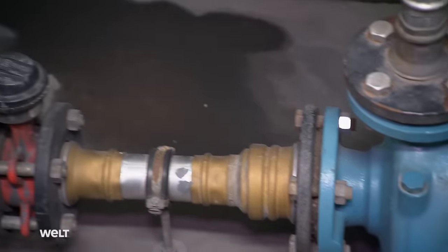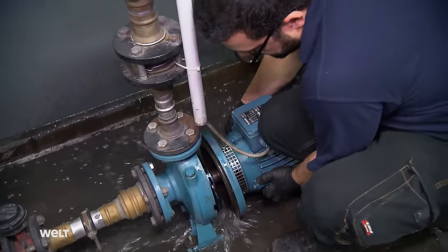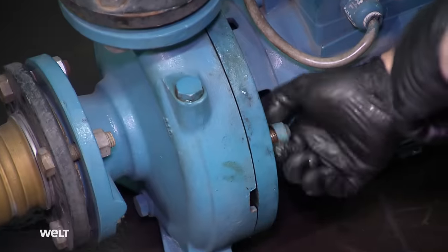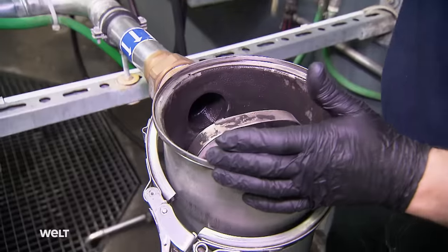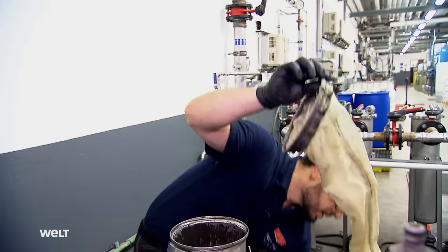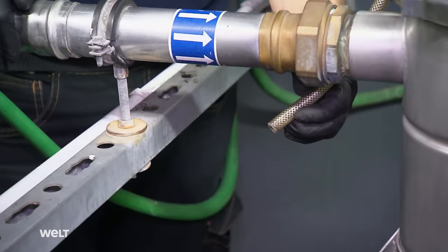Just when the demand starts to peak, there's a problem in the technical room. One of the water pumps for the recycled process water, which transports water into the wash facility after filtration, has a leak — its seal is completely worn out. If we don't repair this in time, the leak will get worse, the pressure could drop, meaning we wouldn't get the volume of water we need. Muhammad Zain must turn off the pump; now the car wash will be supplied with fresh water instead. The operating technician removes the pump's electric engine, which weighs 20 kg. The seals are worn and have to be replaced — a task lasting over half an hour. After reassembling the pump, the operating technician tests the process water filter. The filter isn't looking great — it should be replaced. He attaches the clean filter, fits and secures the lid, ventilates the whole system, and only then can the pump finally return to service.